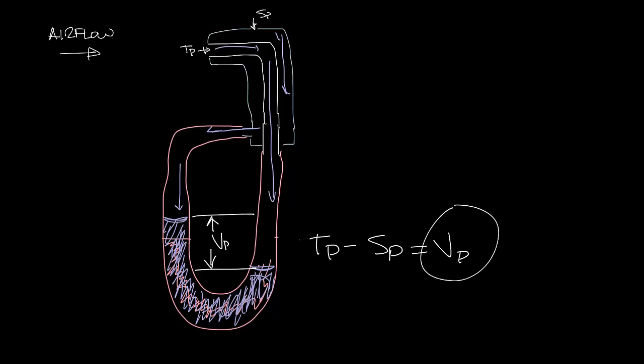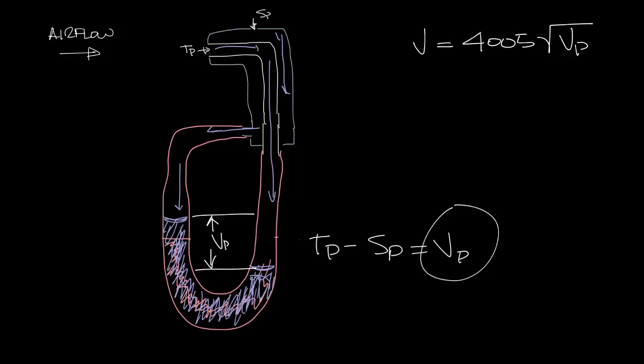And once you know the velocity pressure, you can calculate the velocity, which is 4005 times the square root of velocity pressure. And once you know the velocity, you can calculate the CFM, which is velocity times area.